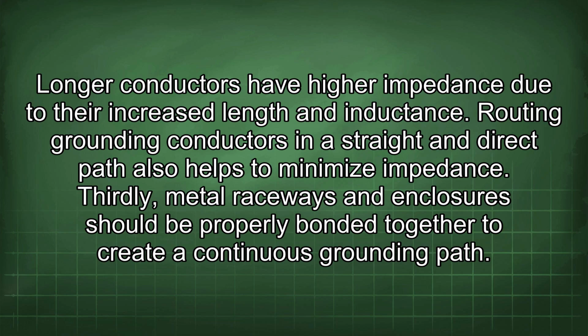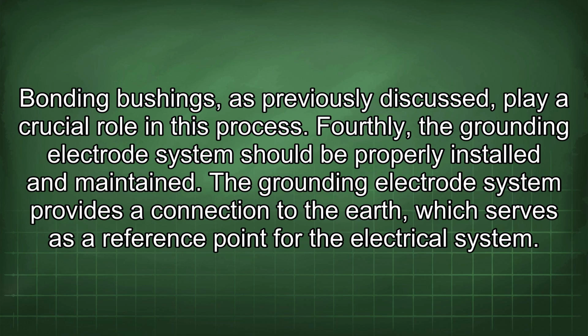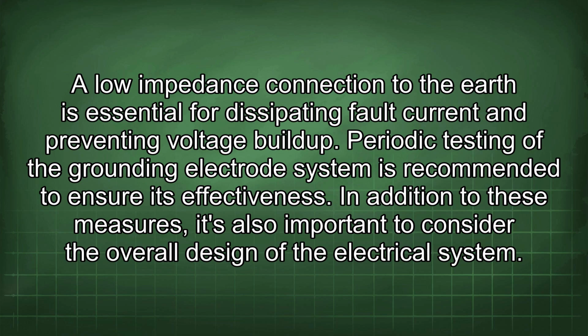Thirdly, metal raceways and enclosures should be properly bonded together to create a continuous grounding path. Bonding bushings, as previously discussed, play a crucial role in this process. Fourthly, the grounding electrode system should be properly installed and maintained. The grounding electrode system provides a connection to the earth, which serves as a reference point for the electrical system. A low-impedance connection to the earth is essential for dissipating fault current and preventing voltage buildup. Periodic testing of the grounding electrode system is recommended to ensure its effectiveness.